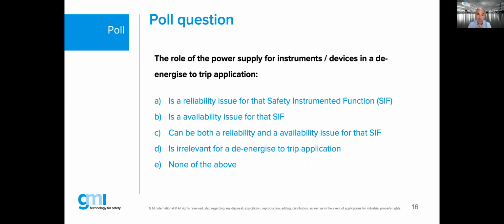That's also the reason why we do this webinar today, because we're going to try to explain this a bit more in depth. Now, why is this an availability issue? Well, there are requirements specific to the vendors of devices and power supplies, who need to think about under voltage, over voltage and inrush current. All those items have to be monitored from the IEC 61508 point of view. I can give you a very practical example of why this became a big issue for a large end user somewhere in Europe. There was an offshore platform that had an overcurrent where the fuse was not blown, resulting in actually damaging the final elements. In other words, when that platform had to go to a safe shutdown, the final elements could not act anymore because, for whatever reason, the overcurrent was not protected the way it should have been, damaging the final elements.